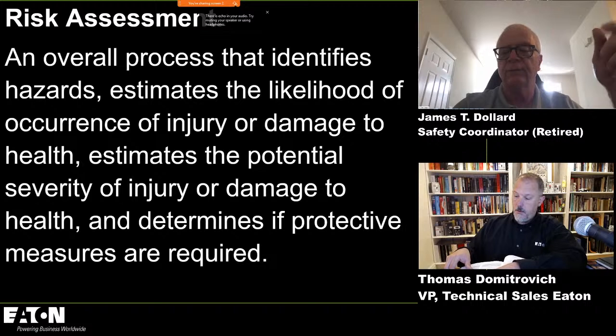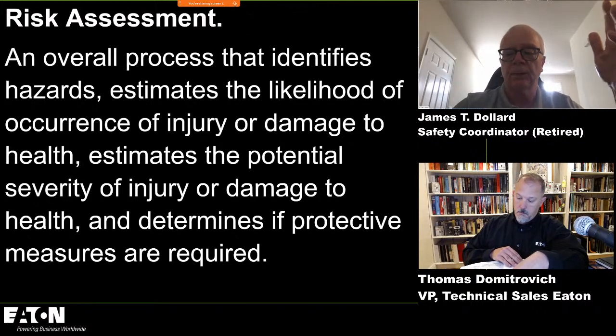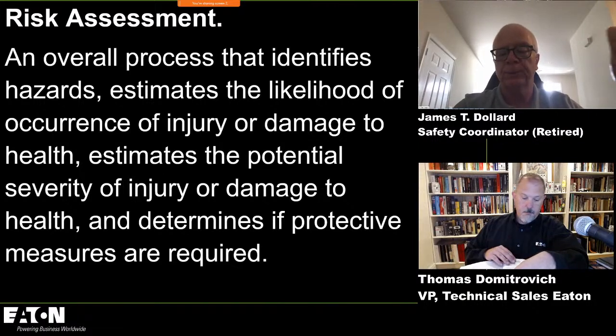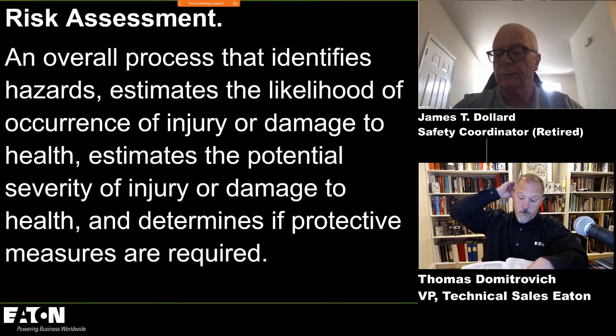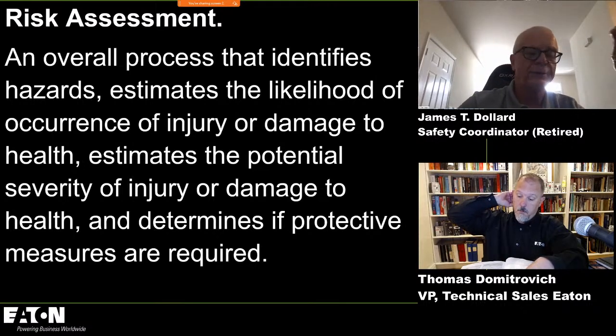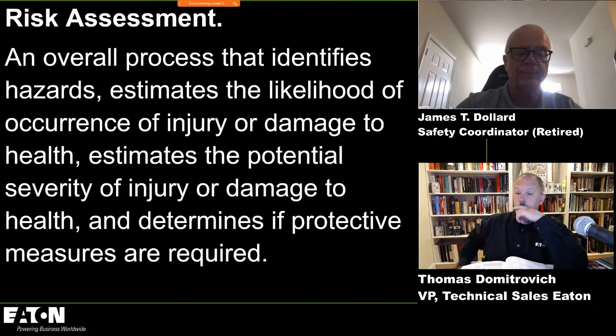And the example that I'll give you there is, is there a likelihood that there is a failure closing a 400 amp molded case circuit breaker? No. But if it does, okay, what's the potential severity? That's completely different than a 4,000 amp low voltage power circuit breaker at 480, 277 that's supplied by service equipment. So you always take a look at both. But the definition of risk assessment is really, really important in 70E, and it's something that we all need to think about anytime we're dealing with a hazard.